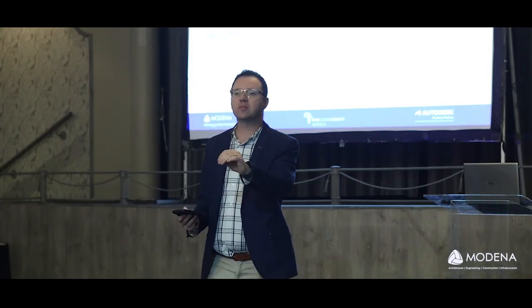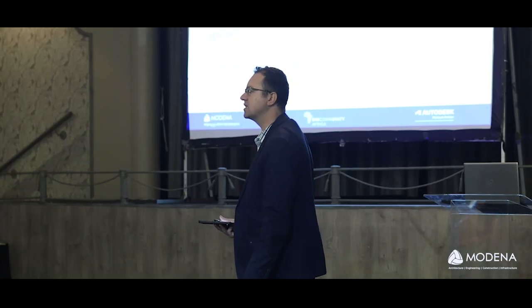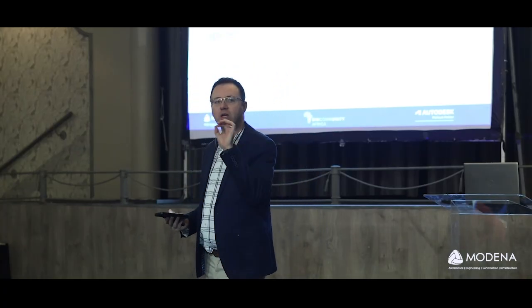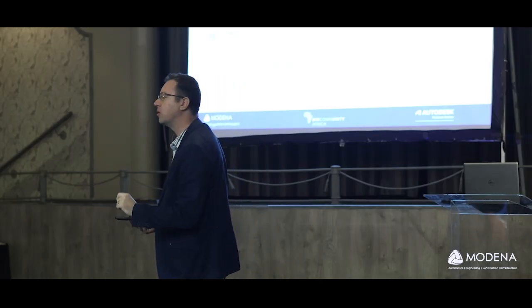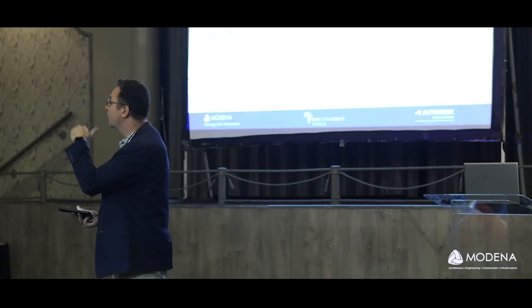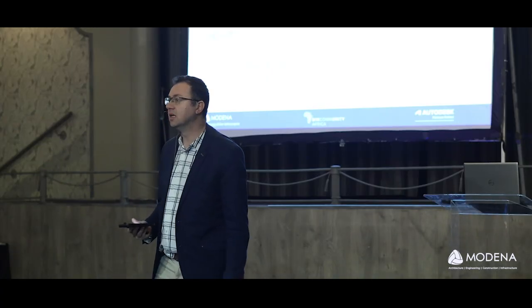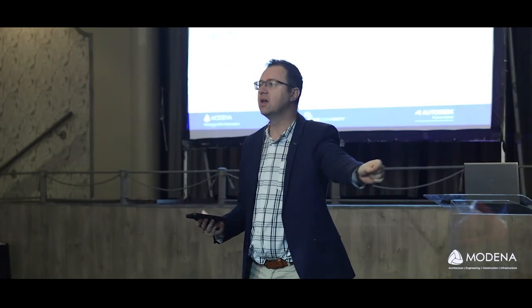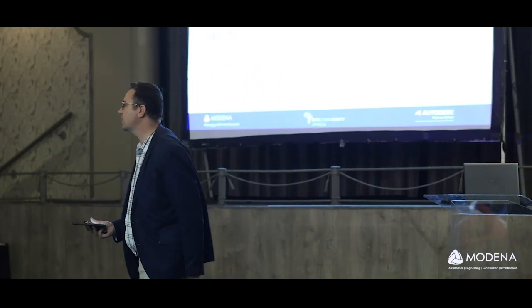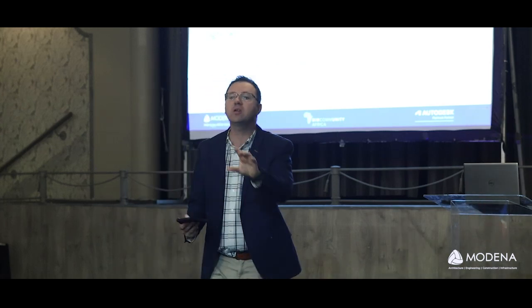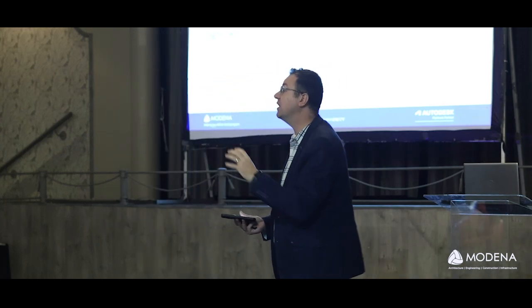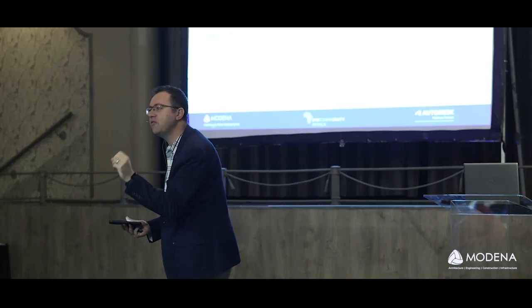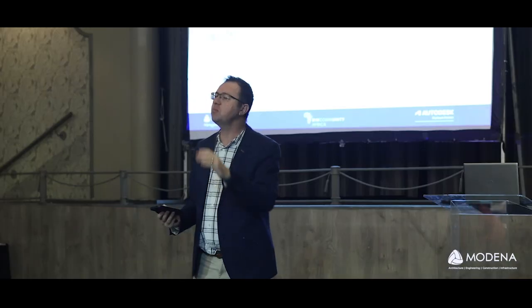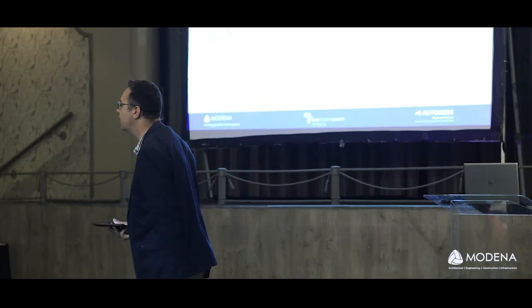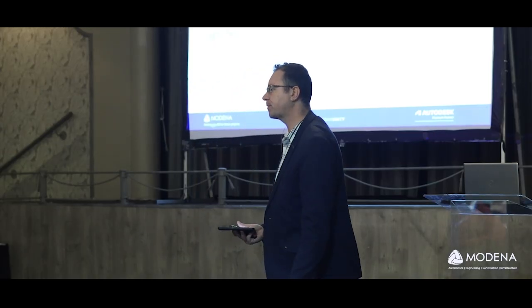He said, over time that light fitting will degrade. In 3 years' time, if we design to 300 lux, we're going to sit with a problem, because the light fitting has degraded and we're under the SANS regulation. Then we're costing the client more money because they have to take out all those fittings and replace them. But if we design to a 350 lux standard, in the next 5 years when it degrades, it's going to be around 300, and we're still in the ballpark figure. So we're actually saving the client money.